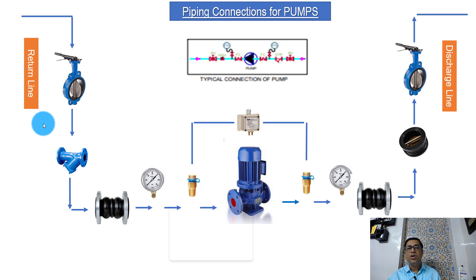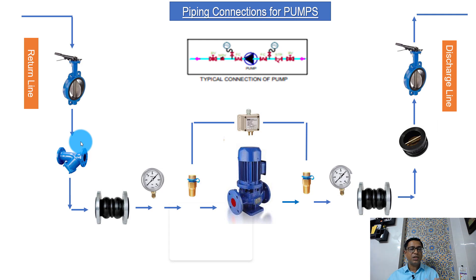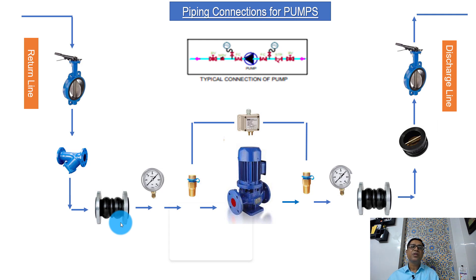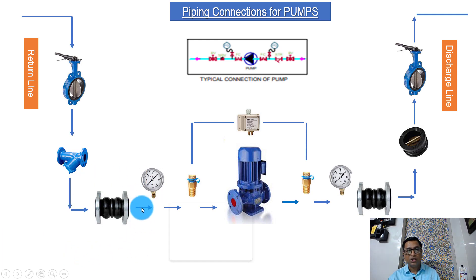Then we get a Y-strainer. What is the purpose of the Y-strainer? To take out the dirt and particles which are present in the flowing water. It has a mesh which actually captures all those particles; we can clean that mesh, remove the particles, and keep the water clean. Then we have a flexible connection. What is the use of a flexible connection? To avoid — or rather reduce — the vibration coming out of the pump to the pipes, because pipes go across the entire building and they will carry that vibration to the structure, impacting the building.